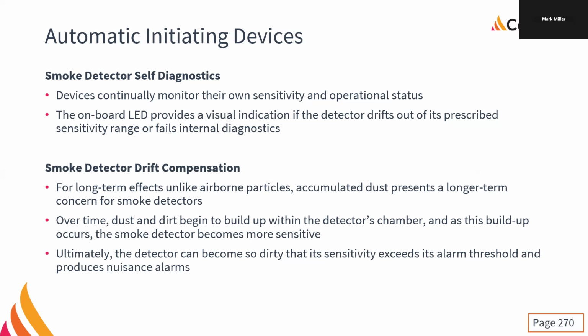Eventually, it's going to get too dusty and dirty in there, and it's not going to be able to adjust anymore, and it's going to try to send a signal. It's going to use the blinking LED light to tell you that it's gone out of range and you need to replace it. Really hard to tell because you have to pay very close attention to how fast and how often that light is blinking. So usually, once you get a few false alarms, you just replace the head.